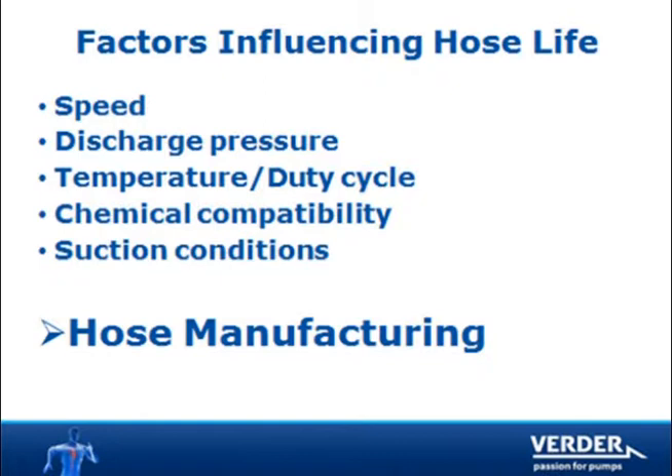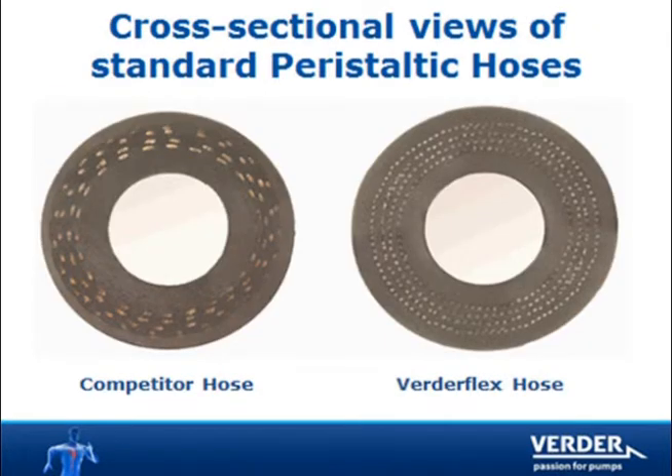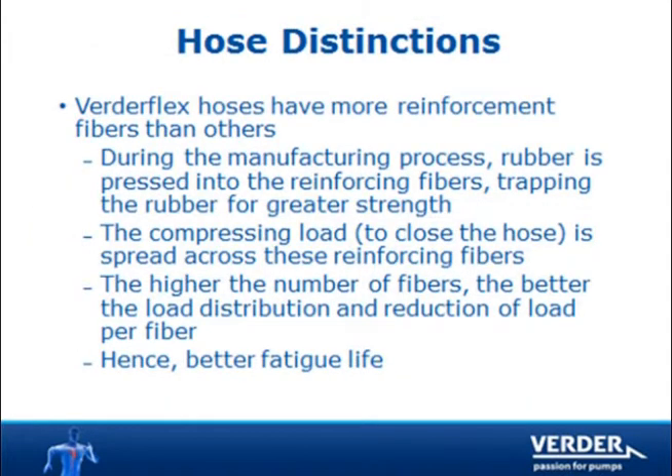It is our proprietary manufacturing process that makes our hose the market leader. As you can see, the Verderflex hose has many more nylon reinforcement fibers than our competition. These nylon layers absorb the compression load as the pump rotor turns. Twice per revolution, the rotor shoes compress the hose, exerting great force. This force is absorbed by the nylon fibers. Since Verderflex hoses have more fibers, the resulting load on each fiber is less, thereby minimizing fatigue and extending hose life.